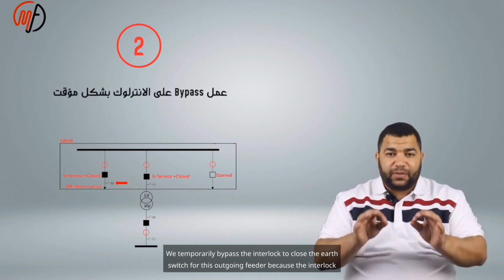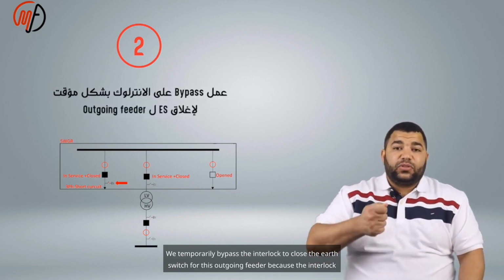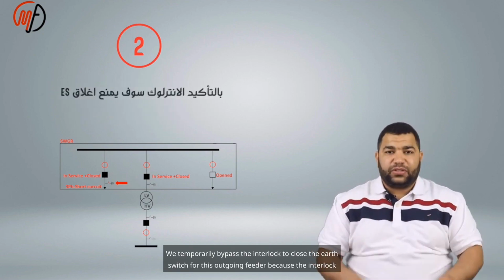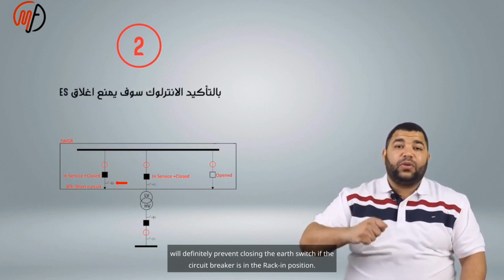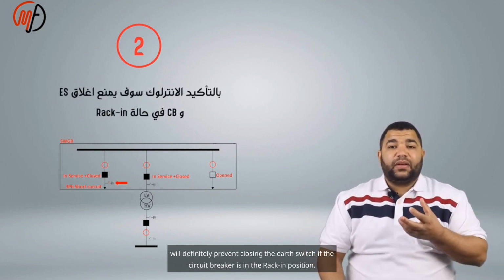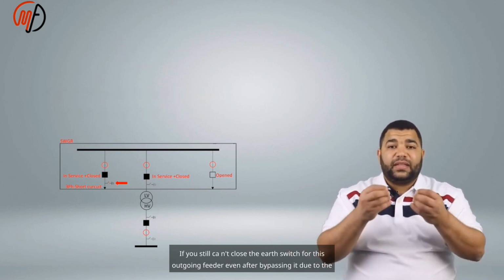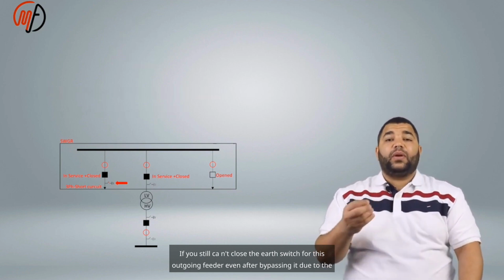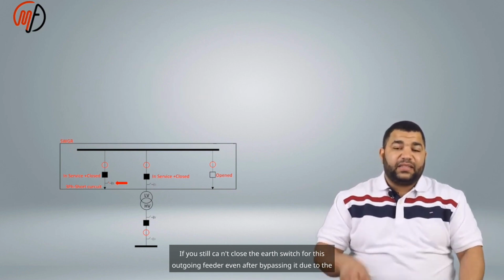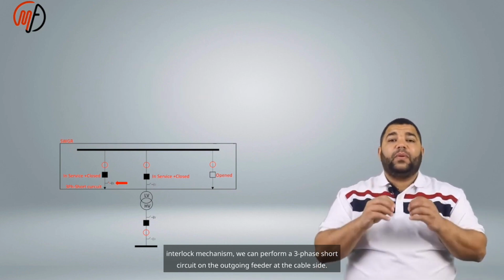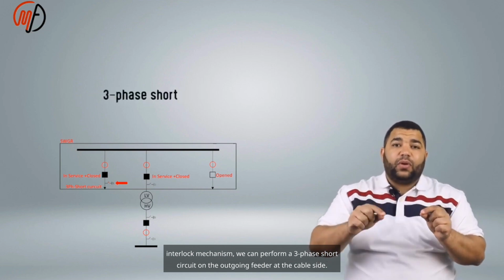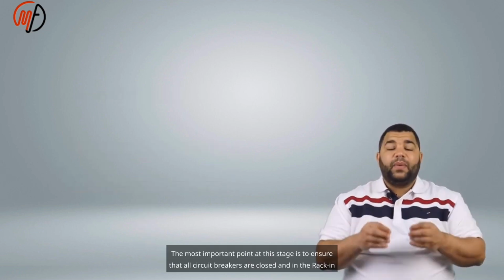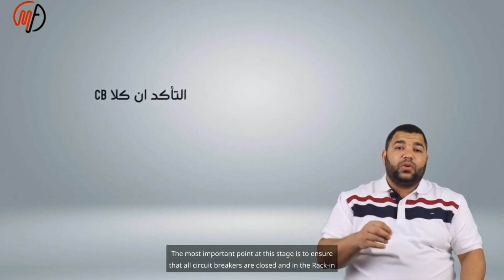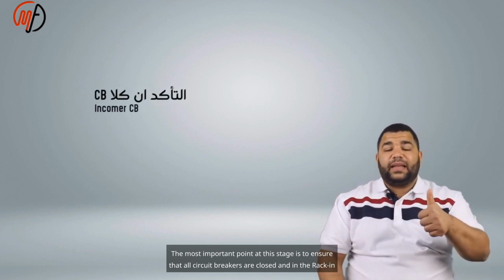We temporarily bypass the interlock to close the earth switch for this outgoing feeder because the interlock will definitely prevent closing the earth switch if the circuit breaker is in the rack-in position. If you still can't close the earth switch for this outgoing feeder, even after bypassing the interlock mechanism, we can perform a three-phase short circuit on the outgoing feeder at the cable side.